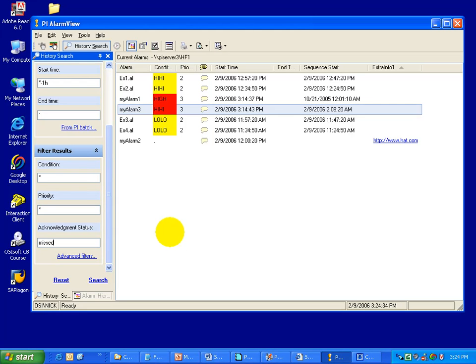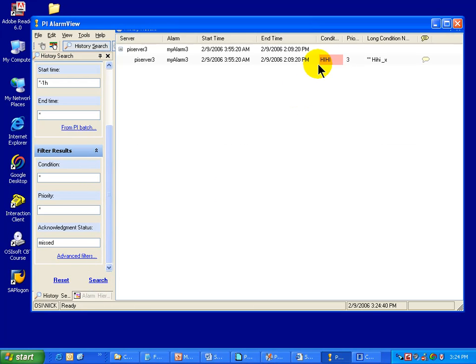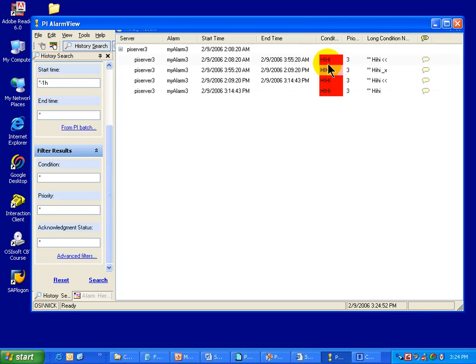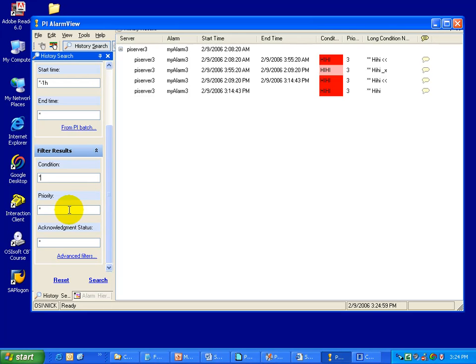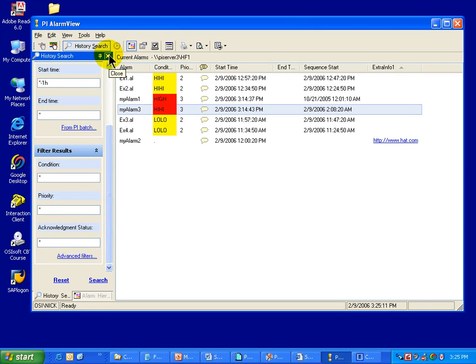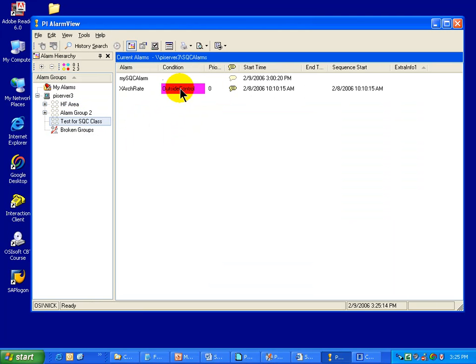For example, I would like to find all those alarms whose status is missed. By choosing Search, we find from that time period that this is a missed alarm. Compare that to doing a raw search — we would see all values, not just the ones that were missed. This can be done filtering by condition, which would be the alarm state like high-high, low, low-low, etc. In the case of SQC alarms, we would be seeing not high-high and low-low, but things like outside control, stratified, trend, etc.